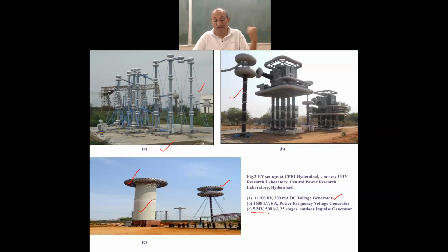3-4 decades the AC power frequency transmission voltage may be needed to the level of 1200 kV. Today it is 800 kV. The next, if India goes for still higher in the next coming few decades, it will be 1200 kV. At present, 1200 kV is not required. Total installed capacity of our power generation can be transmitted very easily with 800 kV at present.